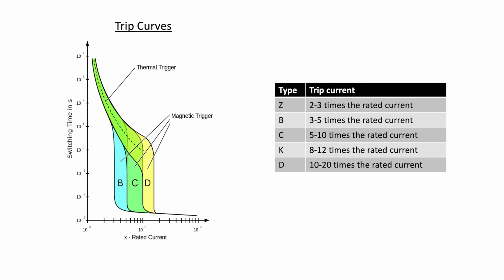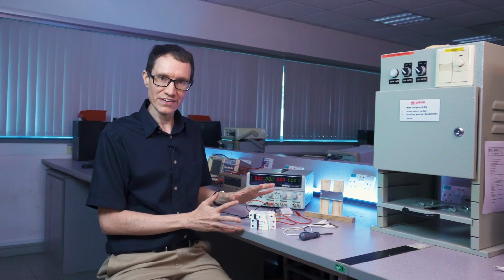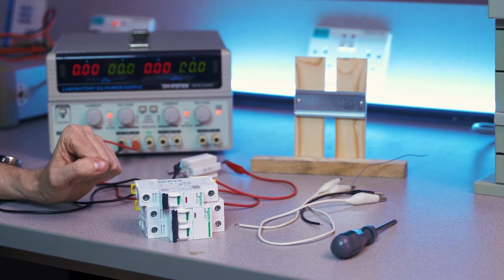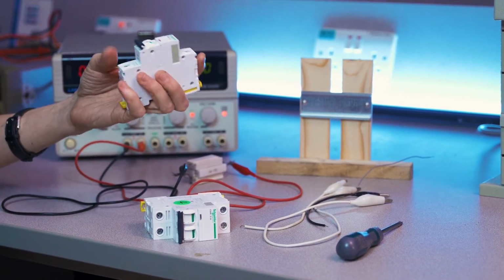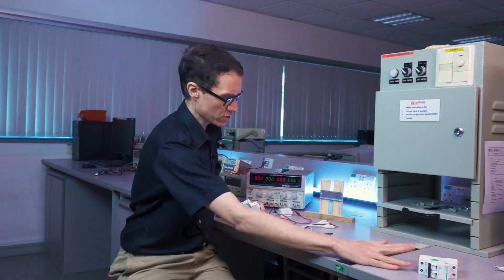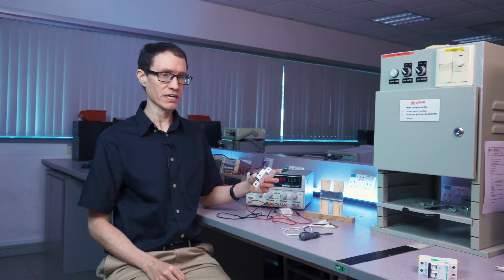That's to protect against short circuits, for example. The thermal trigger happens a little bit more slowly. What we're going to do here in the demonstration is to measure the trip curve for this 1-pole circuit breaker right here. We'll put the 2-pole circuit breaker aside since I'm not going to be measuring that one.